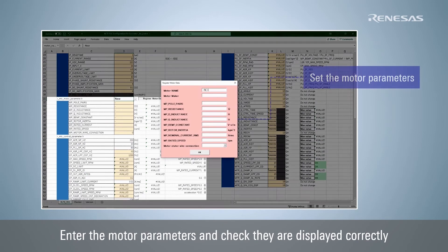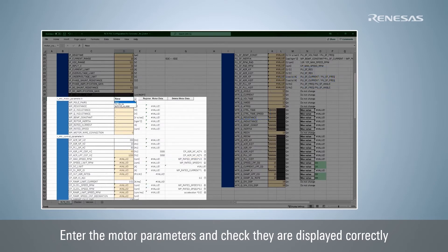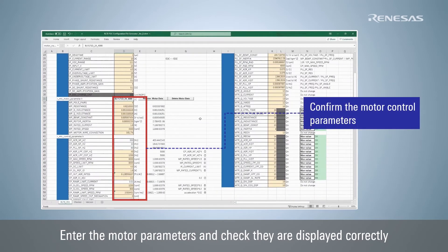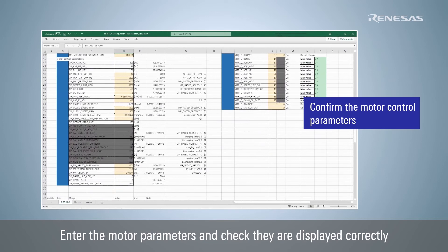Click Register Motor Data and set the motor parameters such as the number of poles, resistance, and inductance, according to the motor characteristics. When you select a registered motor, the control parameters will be automatically calculated for you to check. Fixed values are displayed in white cells, while orange cells display values calculated from the inverter board and motor parameters.